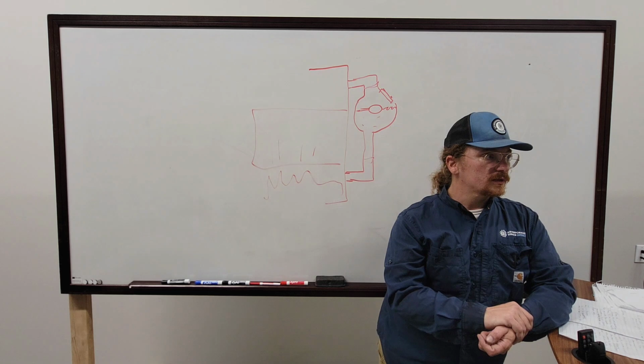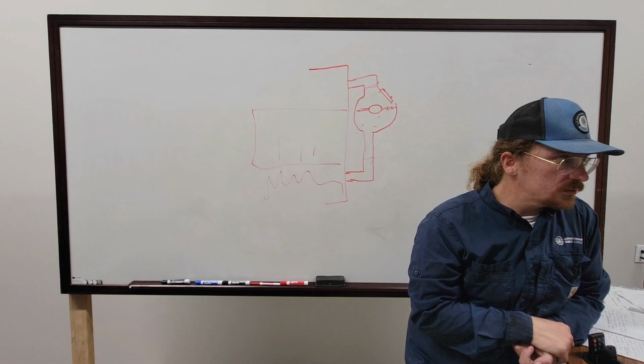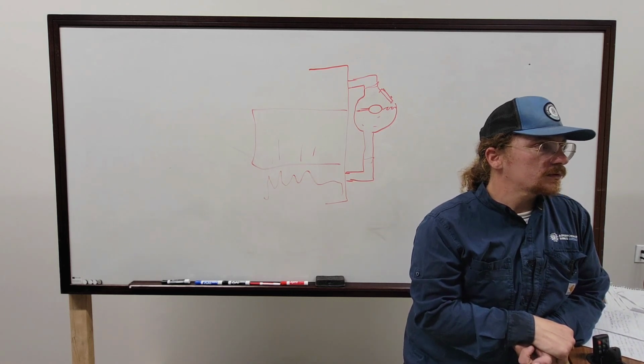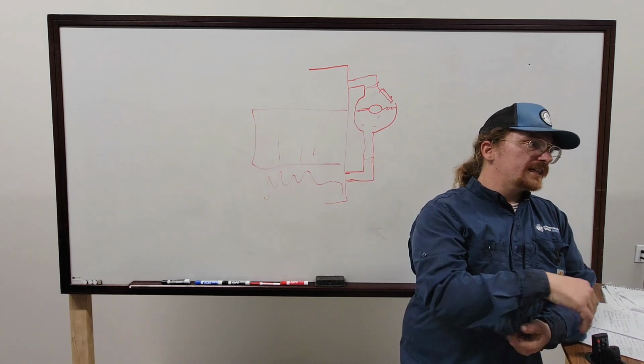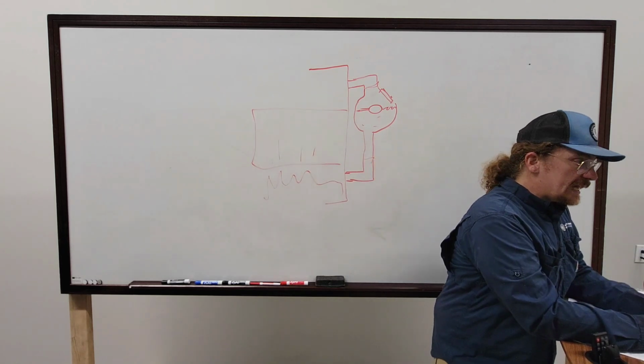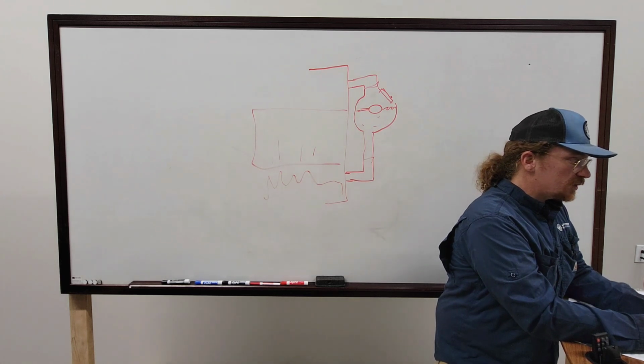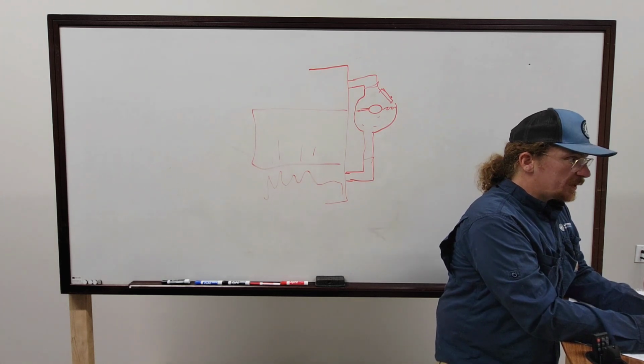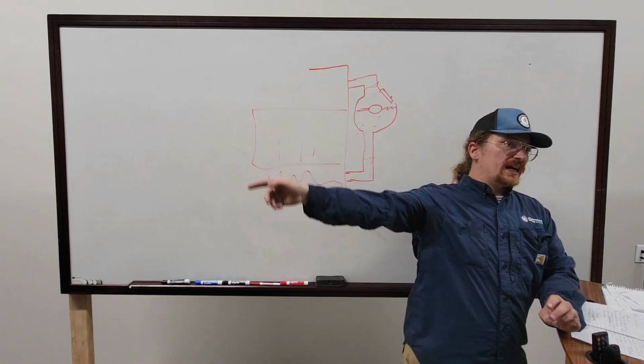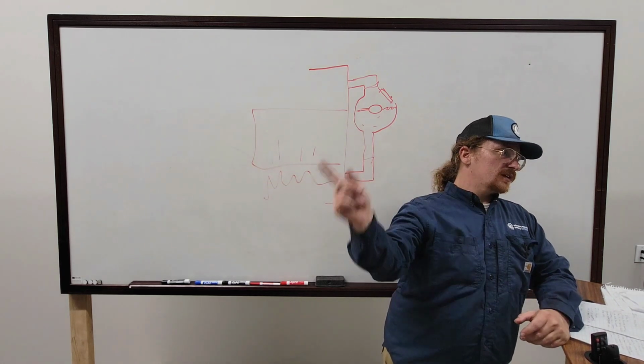Like in the furnace IFC, integrated furnace control, it goes through its eight steps, and then it continuously checks that everything is running right, like your flame sensor. I see. So it's continuously analyzing the situation? In the case of this guy, it's just interlocks. It's just logic. In this case, it was relay logic. Something will open, and then that will open this set of contacts in here. But it's not continuously reaching out to see if we have a flame again. It's not continuously reaching out to make sure we have flow. It is all interlocks. This is safeties.